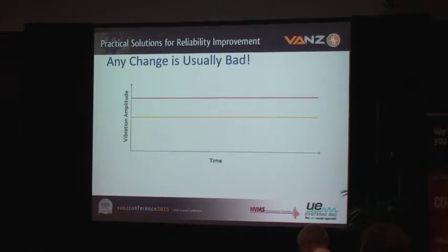So they're trucking along, and they've got indications of vibration on some machinery in the control room. And what they're looking at is the overall vibration amplitude. So as time marches on, they're looking at this, I mean, it varies a little bit. But just for the sake of simplicity, we'll treat it like a straight line. All of a sudden, one day, they noticed that there had been a change. There was an increase in the amplitude. Step change. And it leveled out. And it ran that way for about a day.